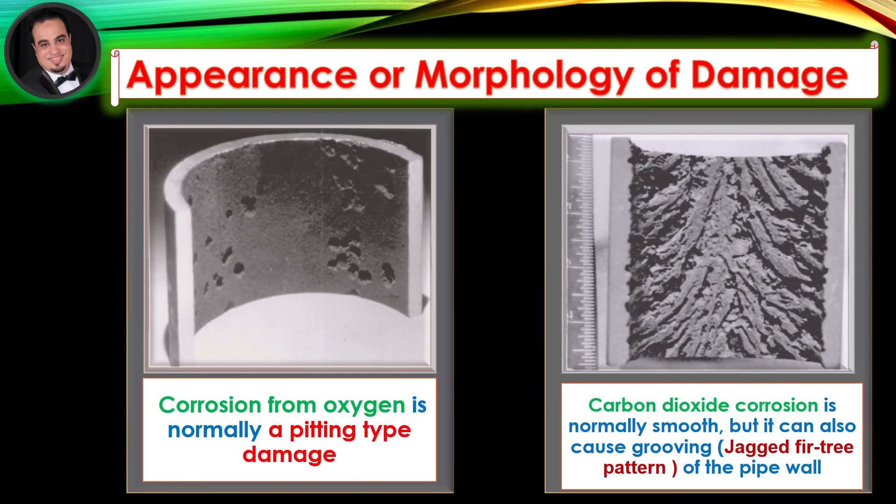Appearance or morphology of damage. Corrosion from oxygen is normally a pitting type damage. Carbon dioxide corrosion is normally smooth, but it can also cause grooving — a jagged fir tree pattern of the pipe wall.